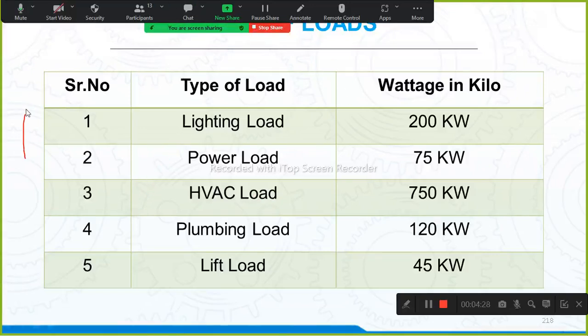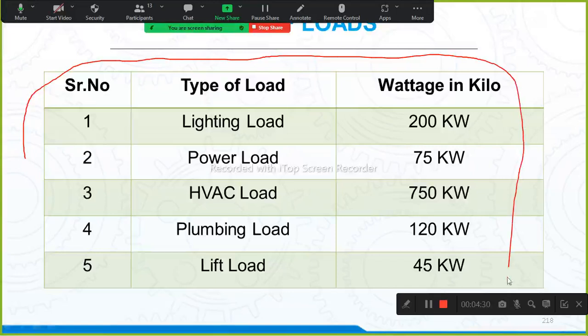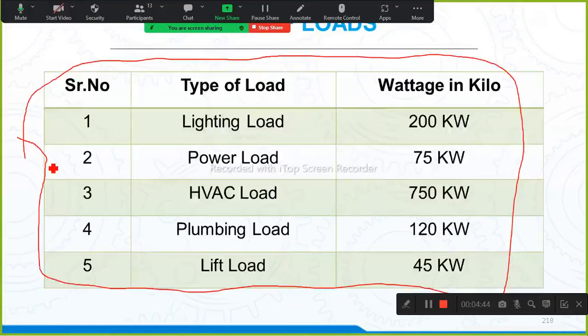Okay, this is my total connected load for the building, that is your MDB load, which consists of lighting load of 200 kilowatt, power load of 75 kilowatt, HVAC load of 750 kilowatt, plumbing load of 120 kilowatt, and the lift load which is 45 kilowatt. This is the total load. Now we need to calculate the transformer size. There are 12 steps of calculation for defining the transformer size.